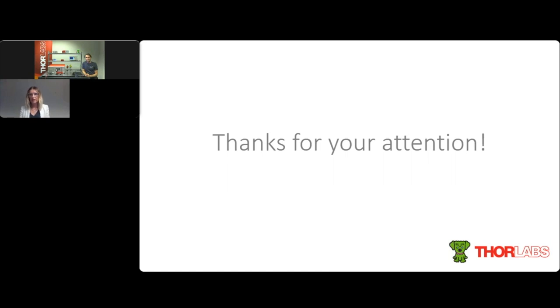What kind of pulsed sources can the Redstone measure? That's also a good question. We have a lot of customers with pulsed sources. And I would say that the most important characteristic of a pulsed source to determine whether or not we can measure it with a Redstone OSA is the repetition rate. If your repetition rate is above 7 kilohertz, actually, in fact, down to maybe 1 kilohertz, if your wavelength is right, then there are no problems. If it's below, then you may need to make sure that this special pulsed mode operation works. Maybe you should just contact us to make sure that your application will work, or you can borrow a unit to try it out for yourself.